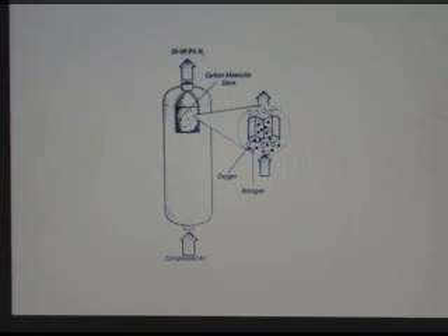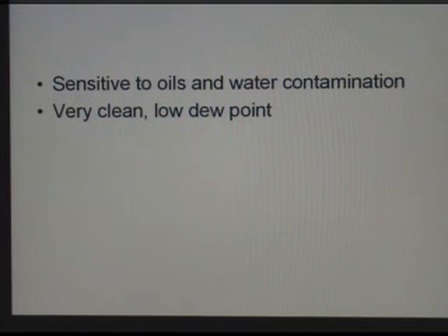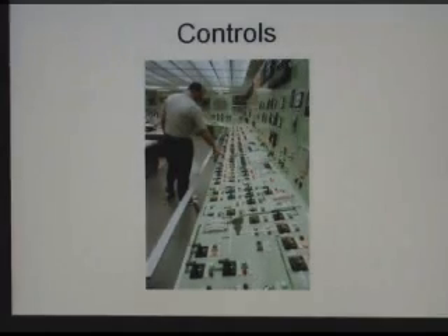And the PSA, compressed air comes in, gets adsorbed into the bed, the carbon molecular sieve, that's the term. And then high purity nitrogen comes out. They're both sensitive to oils and water contamination, which is why we're using instrument air. You don't just hook it up to any air compressor. But it's very, very clean, a very low dew point. Controls.